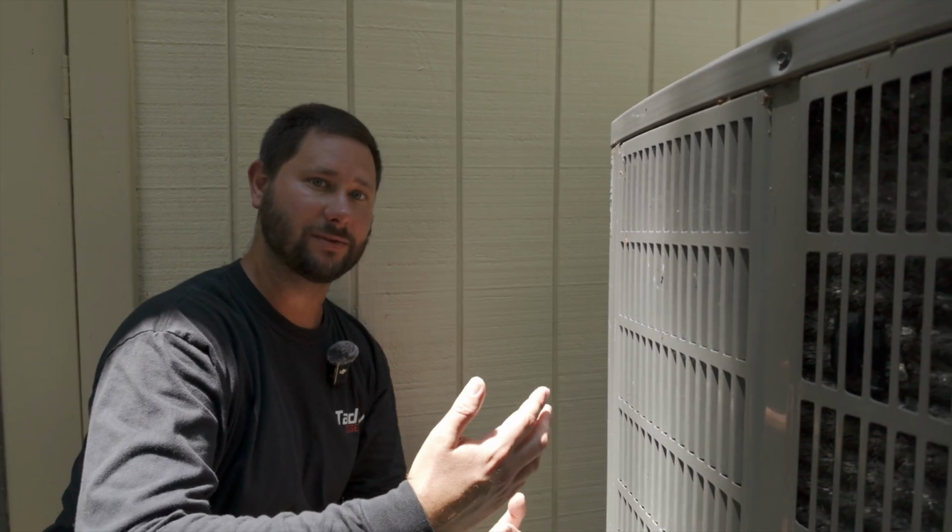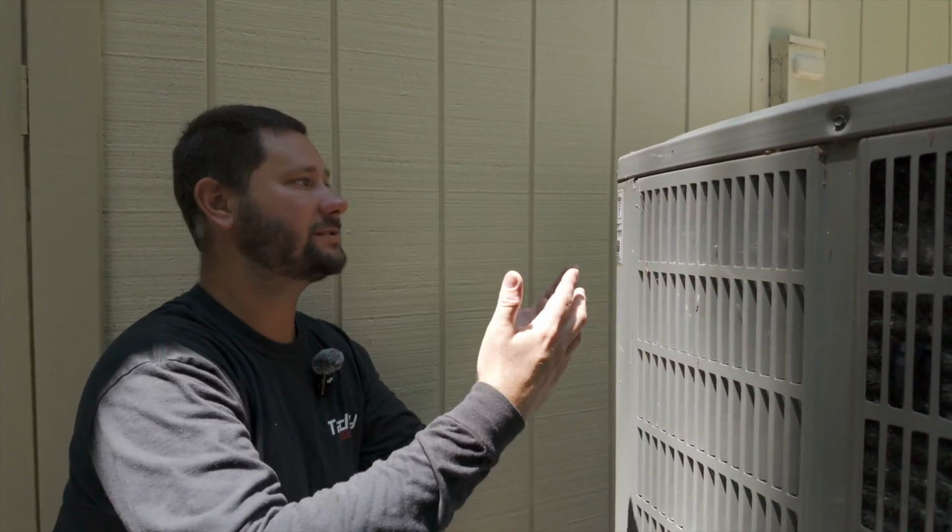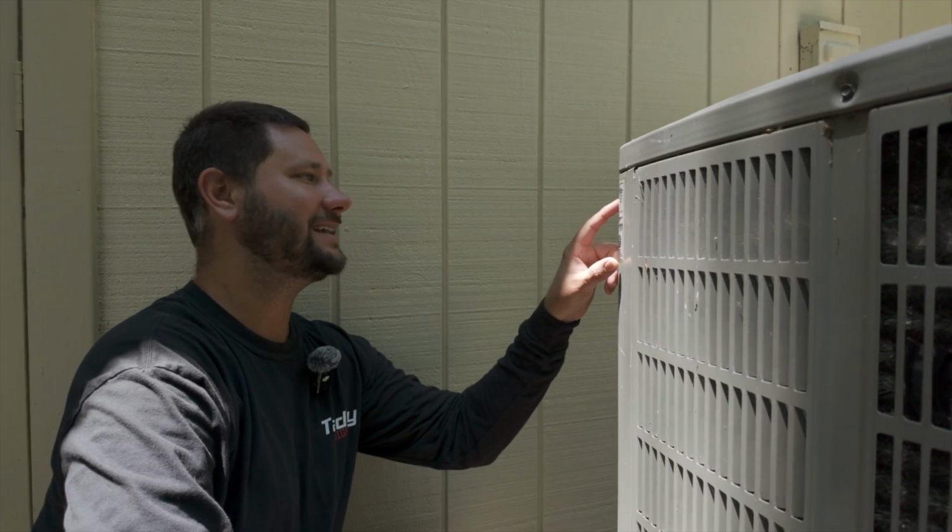2A6H3060. So it could be a 2.5-ton, 30,000 BTU, but judging by the size and the way we should read this American Standard model number, this is a 60,000 BTU unit. So 60,000, that's 5 tons. This is a 5-ton unit. Now let's go back inside and figure out which return grill we need for this 5-ton unit.